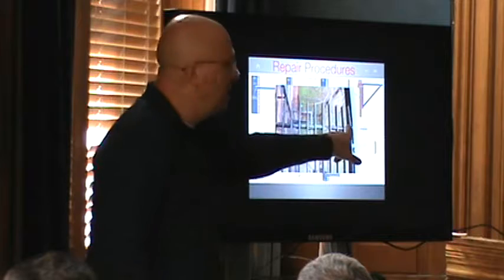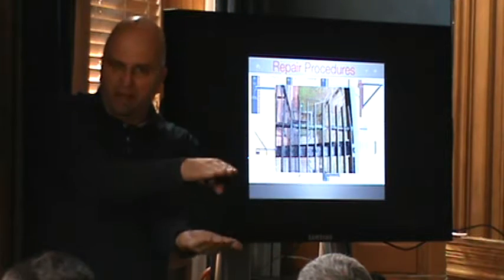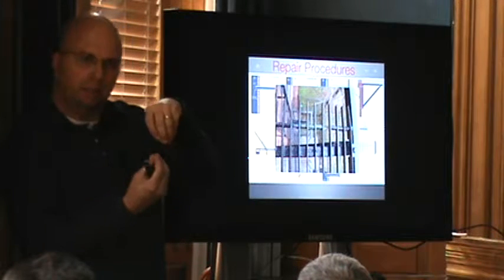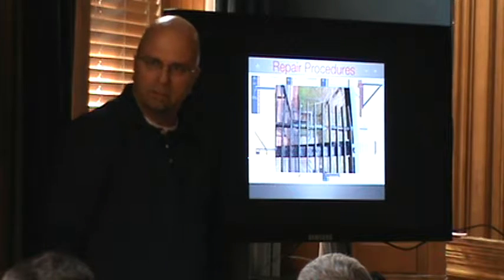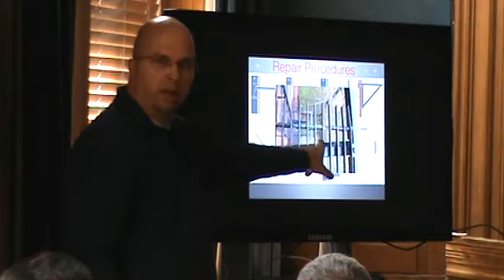Can I get another 5 years out of this piece of grating? Yes. If I can put a piece of flat on top, a piece of flat on the bottom, and then every 6 inches or so there's a carriage bolt, top head, and I basically squish to create a sandwich. Will I guarantee this back to the client? No. You've got a pre-existing structure, but I can reinforce it so that it doesn't separate. But we should replace all your grating and all your treads that have these spacers inside with a new style of grating that doesn't have any of these spacers. They look like this inside when they're rotting.